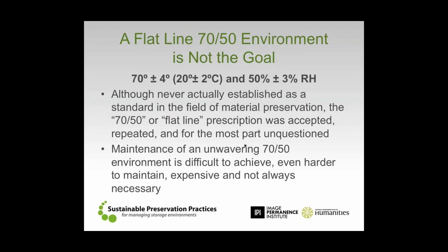And even though that 70-50 or flatline condition was never officially established as a standard for preservation in libraries, archives, and museums, quite often that stated range, 70-50 plus or minus just a little bit, was generally accepted throughout the field. And as time has gone on, not only has it been accepted within the world of collections and preservation, but from the architect and engineer perspective it has also been accepted as part of our design bottom line. And that's something we want to talk about a little bit today as we go through.